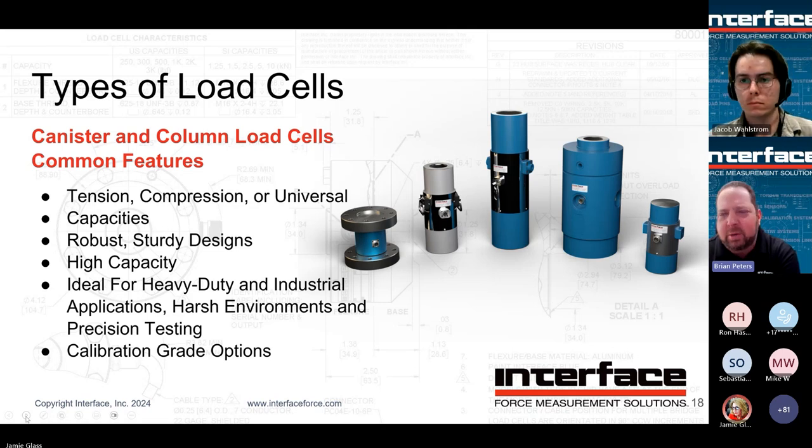Linearity and such may not be quite as good as some other models, but if you can scale that in your instrumentation, it's a non-issue. But again, we can seal them pretty well. That second unit in from the right, the all blue one, has very high hermetic properties, fully welded construction, Class B connectors, for example. So we can develop these into different ultimate form factors depending on what's required for the application.